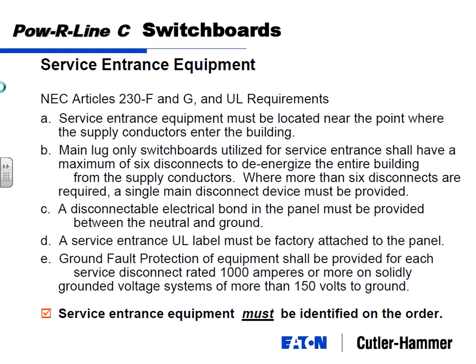There's a bond between the neutral and the ground that is part of the service entrance requirement. Think about that. Keeping the neutral and the ground bonded inside prevents stuff from flowing back out to the transformer on the neutral, the transformer being owned by the utility.